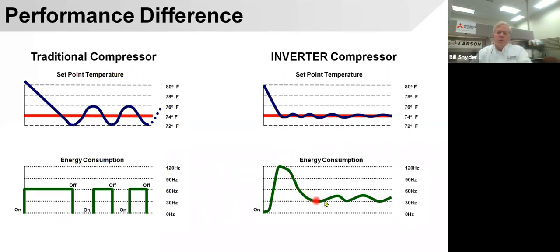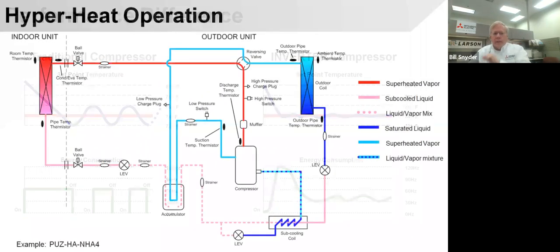We slow the compressor down, we speed it up a little bit, we slow it down. But you'll notice there are no off cycles. Typically, on a warm day, this compressor will run all day long, but instead of running at 60 hertz, we're slowing that down to, in this case, around 30 hertz. Conserving energy, yet keeping a cold coil, which helps to dehumidify and makes the space more comfortable. Okay, so how do we do this?